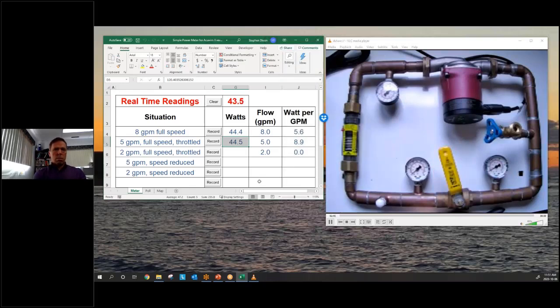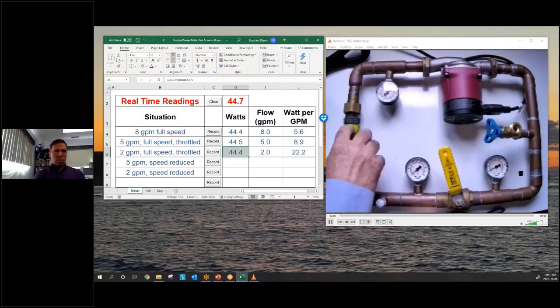So we're down a little bit, okay? But we're basically running the same power to do the same thing. It's funny, I've seen these pumps in hydronic systems, this particular pump with a throttling valve on it, and the pump was set to full speed like it is now. So that pump is still running at full speed. The noise you heard was actually the rattling of the spring in this pump. But now, which one do you want to pay for? Well, you're not getting much flow out of this one, and you're paying a lot for the power.